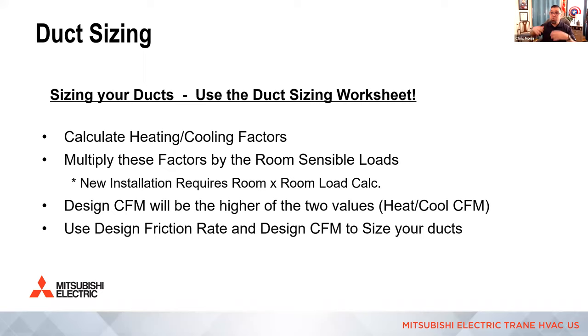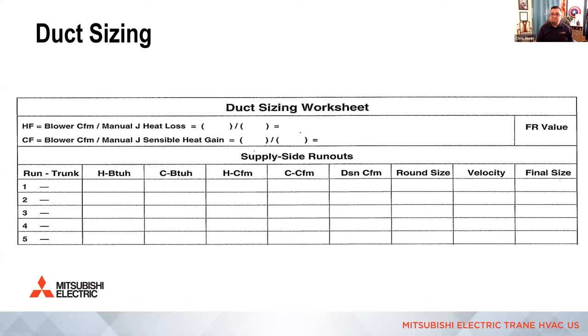And just because you need more total volume of air on, let's say, a furnace with an AC or heat pump add-on, doesn't mean we always design around the cooling CFM, right? When you do the runs first, you're going to find sometimes it's around heating needs for the room, sometimes it's around cooling needs for the room. And that's why we put balancing dampers in, right? And then, of course, we're going to use the design friction rate, then that calculated design CFM, to actually size those duct runs, okay?